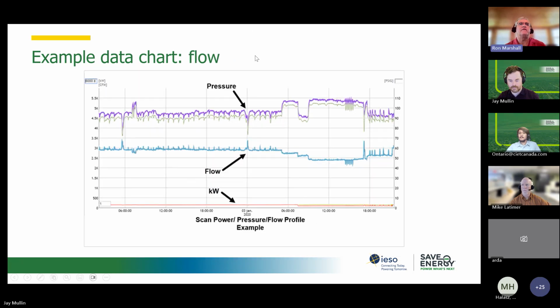Next chart is we add flow to it. I've moved the kilowatts down lower so we can understand what the flow is. And this flow chart confirms what I was suspecting, right? We can see with those low pressure dips, there's a high flow increase, right? So that shows that those dips are caused by flow. And we can also see as the compressors unload, the flow is going down, and we can see the sawtooth waveform where the compressor is loading and unloading. So three things on the chart that help us understand what's happening on the system, and we can troubleshoot problems.